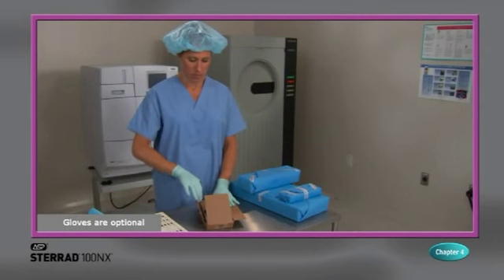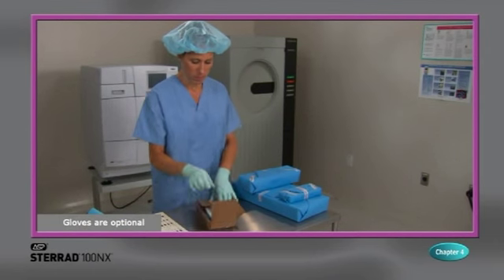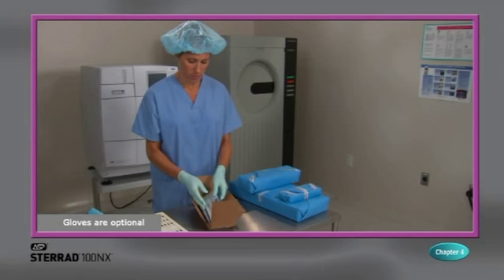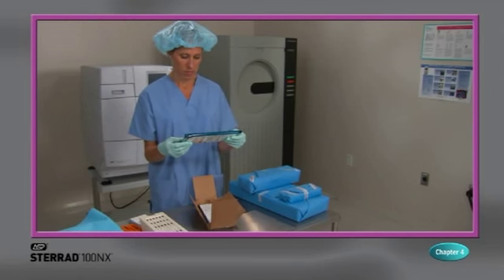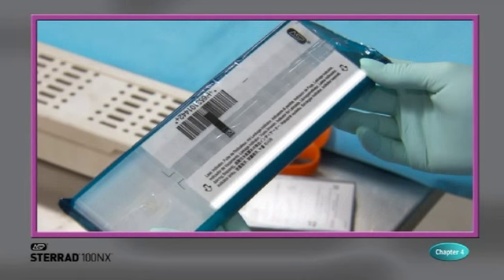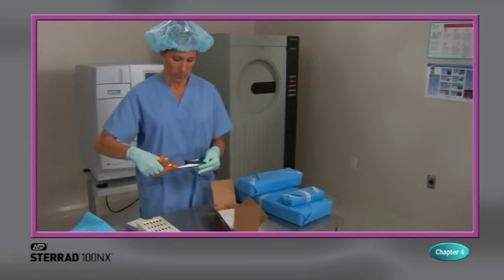Take a new Sterrad 100NX system cassette out of the shipping carton. Look at the package carefully before opening it. The indicator strip should be white. If the indicator strip is red, or if you see droplets of moisture, do not open the package. It's possible that hydrogen peroxide has leaked inside the package. Refer to the cassette Instructions for Use for proper handling instructions. If the indicator strip is white, open the cassette package.